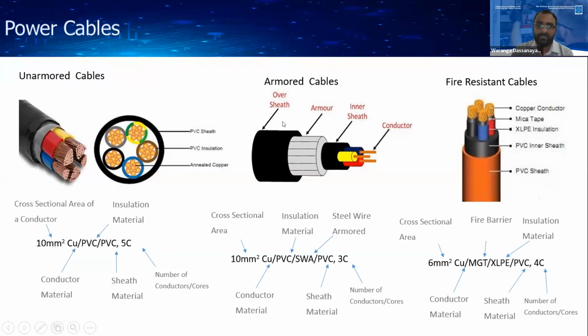So the next type is armored cable, as I explained earlier. Outside the inner sheath there is a steel wire armor to protect the inside conductors from mechanical damage. Basically, this kind of cable is used in heavy industry or factories, where the cable can be damaged by hitting from moving equipment or very heavy loads.